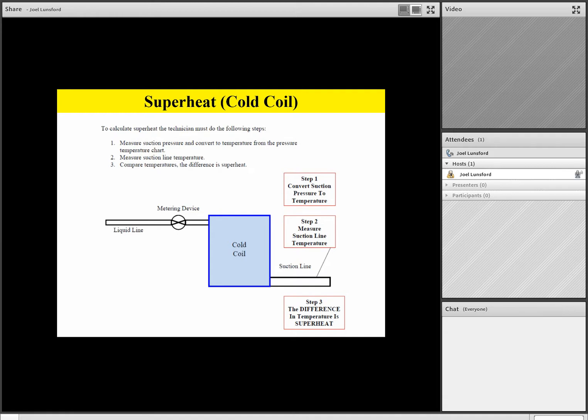If the superheat is about 10 to 15 degrees in the cooling mode of operation, we'll consider that normal. And anywhere between about 4 to 15 degrees in the heating mode of operation will be considered a normal range for superheat on the cold coil.